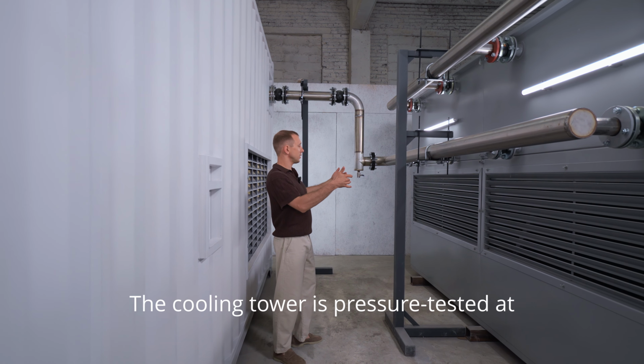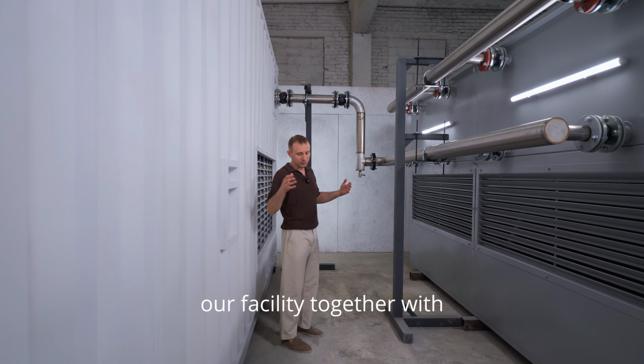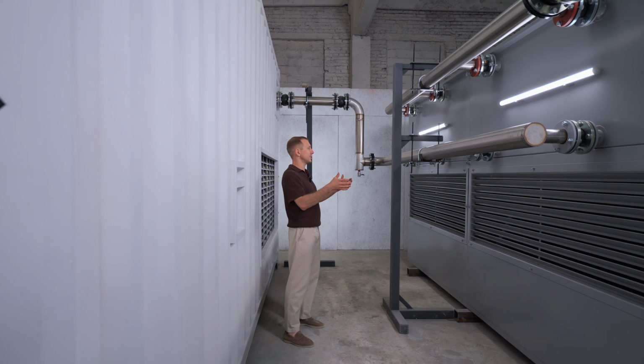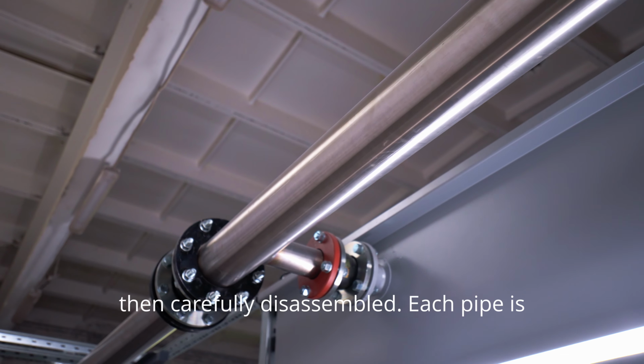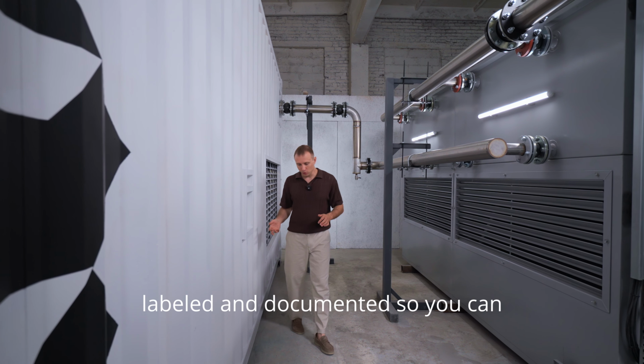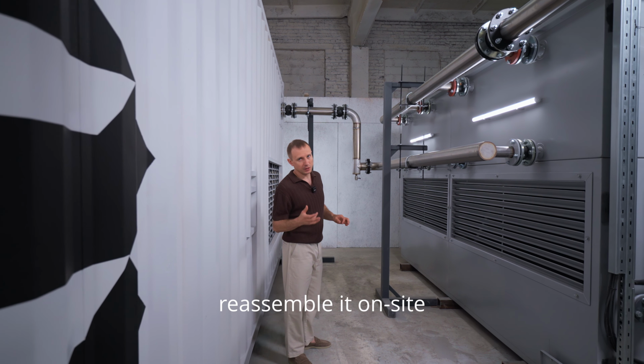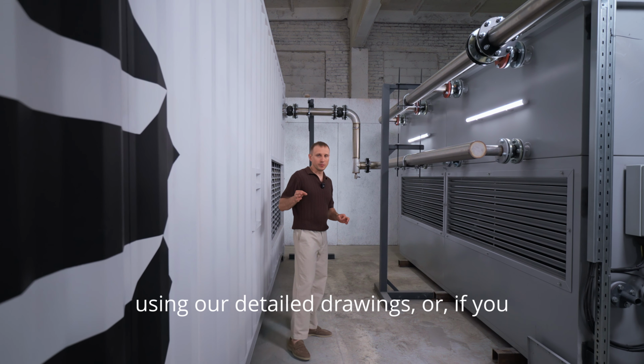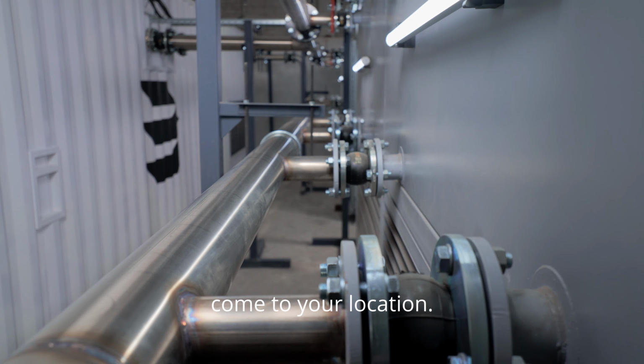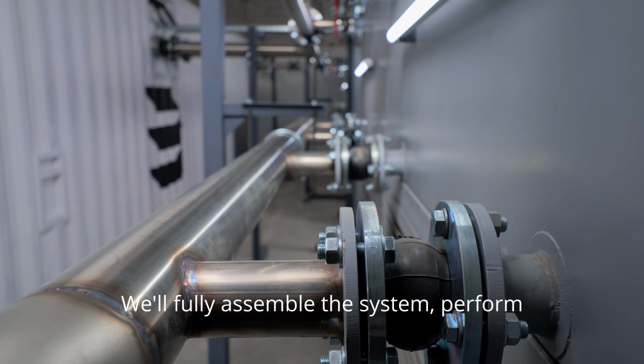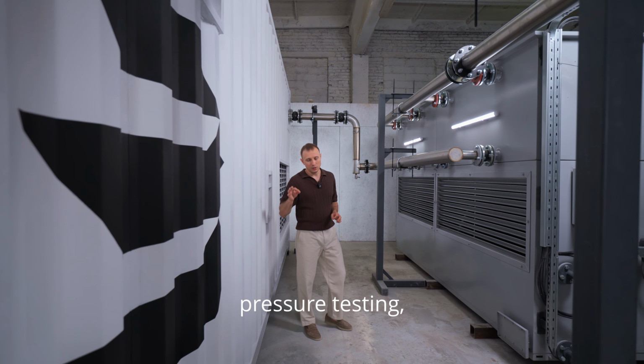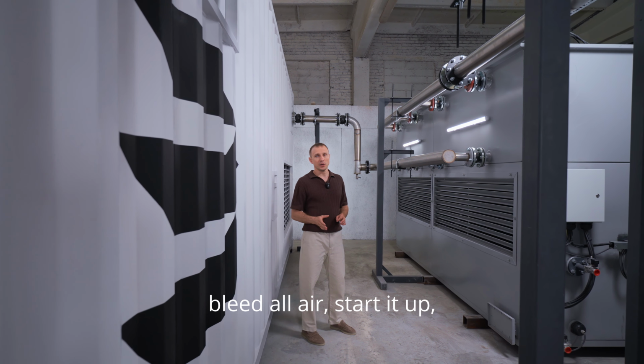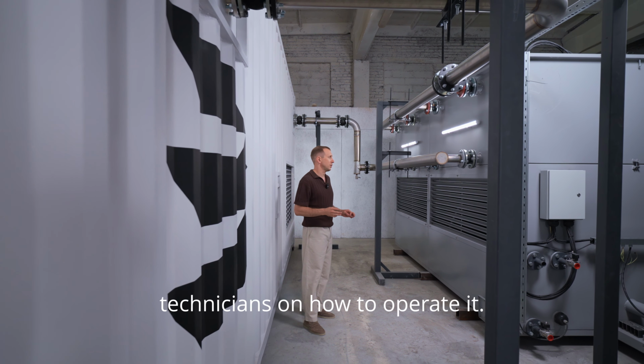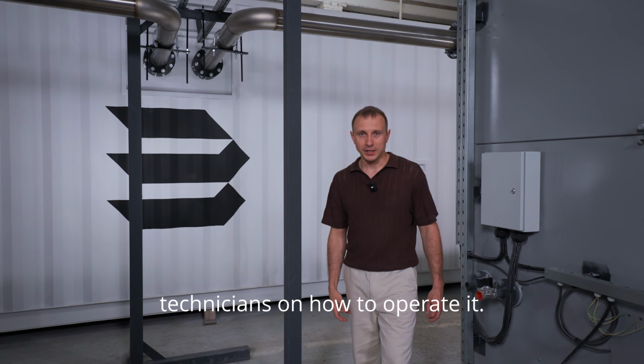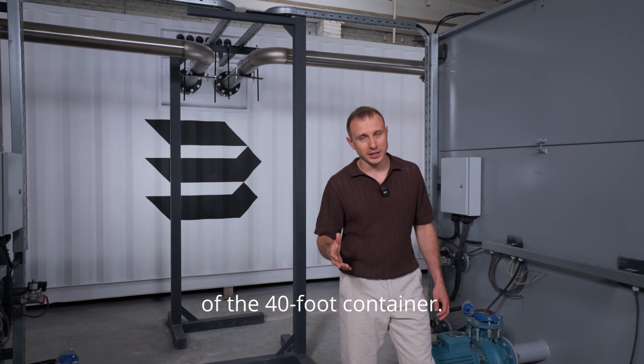The cooling tower is pressure tested at our facility together with the full hydraulic system, then carefully disassembled. Each pipe is labeled and documented so you can reassemble it on-site using our detailed drawings. Or if you prefer, our team can come to your location. We'll fully assemble the system, perform pressure testing, bleed all air, start it up, and train your technicians on how to operate it. That concludes our review of the 40-foot container.